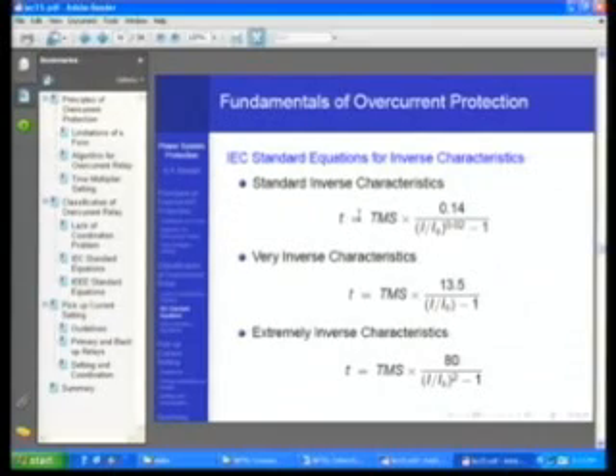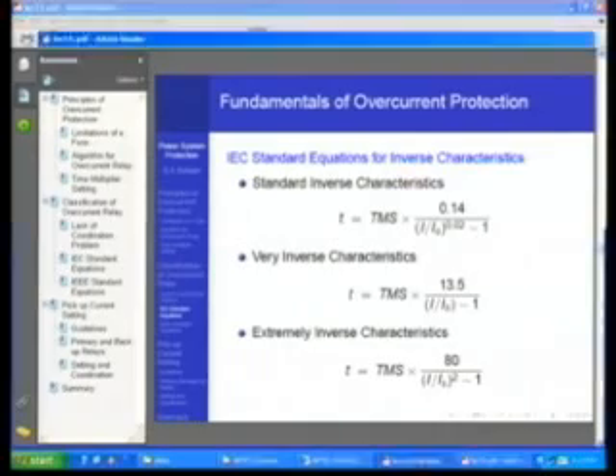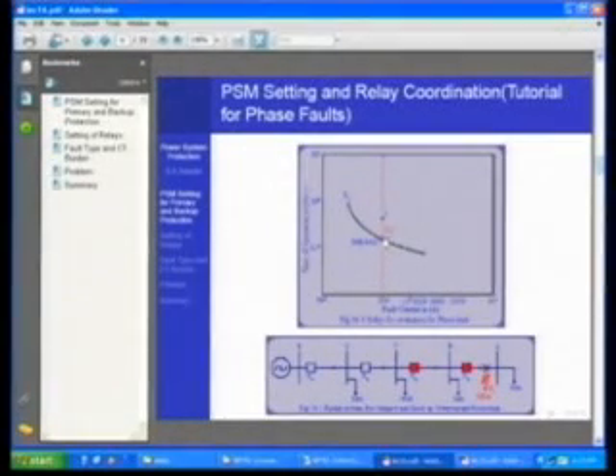What I am saying is you know the relay operating time from that graph. You know the pickup value. So once you know this, the only unknown is TMS. So you solve this equation and calculate the TMS value. That's all I am saying. Is that clear? I found out, by adding 0.3 to this operating time, what the left hand side is.